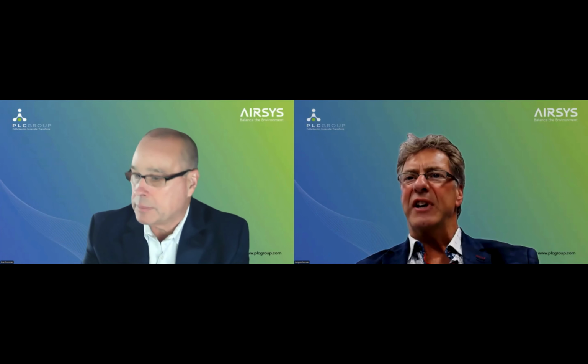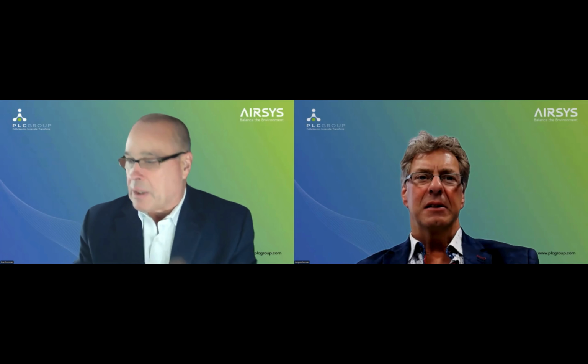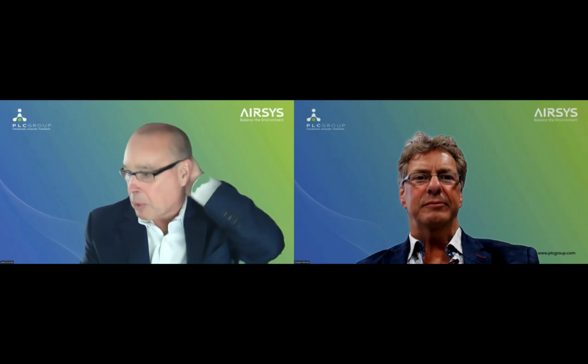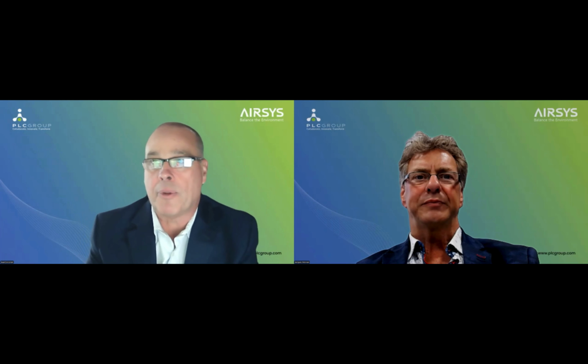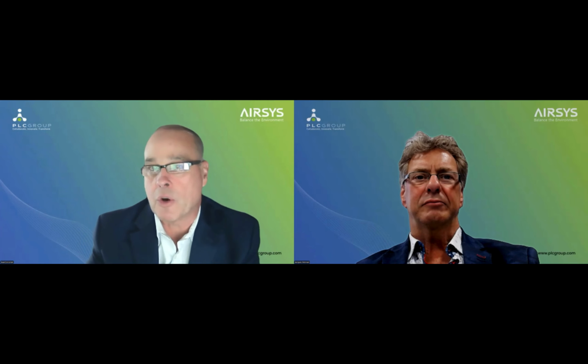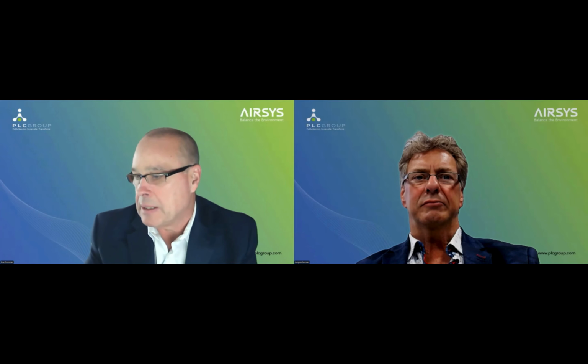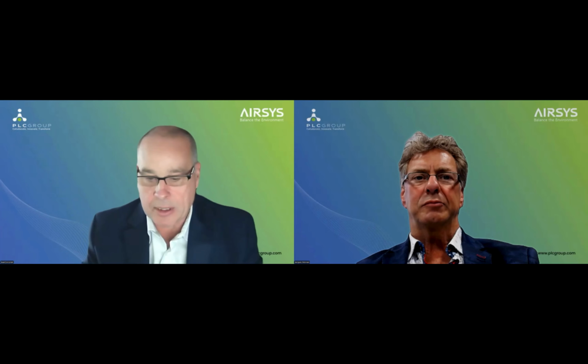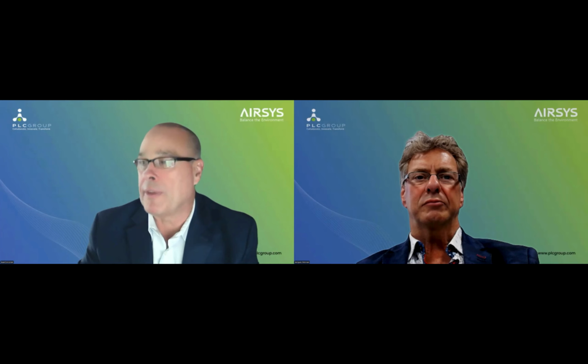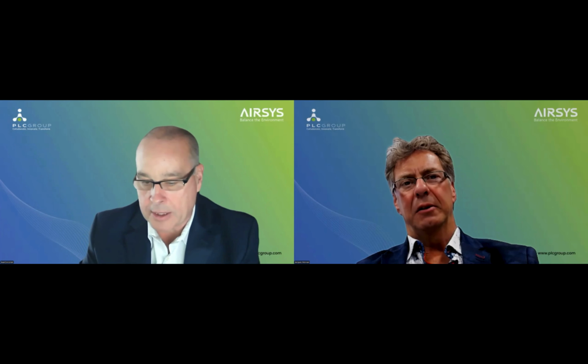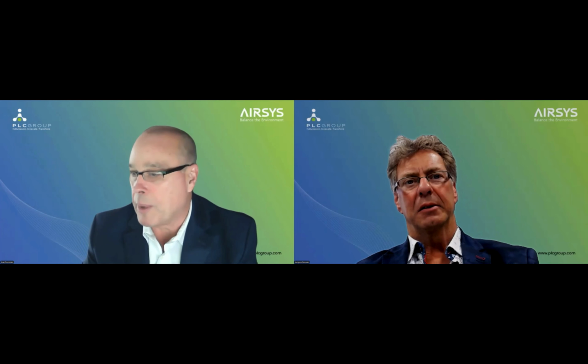What are the common challenges faced during the deployment of Airsys cooling systems? What best practices are recommended to ensure optimal performance? Right. So some of the common challenges of deployment are sometimes site specific. Sometimes getting to the site, sometimes the partner may not have measured correctly. The best practices for optimal performance is ensuring that the pipe lengths, pipe runs, pipe diameters are all within the IOM manual for the product set that we manufacture, and that it conforms and is not outside of the requirements that we have for our product set.